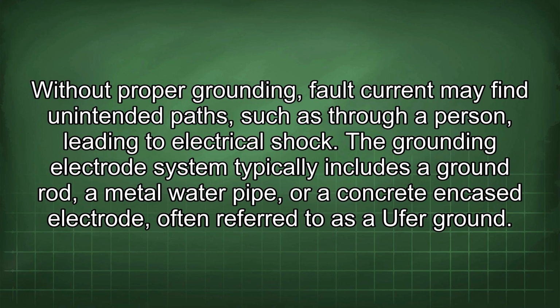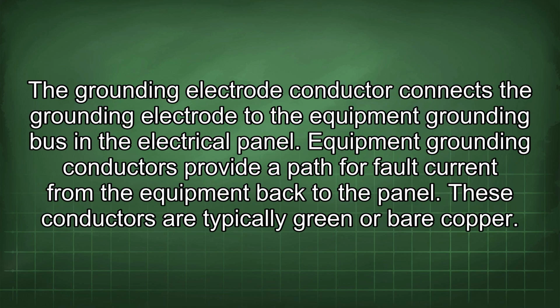The grounding electrode system typically includes a ground rod, a metal water pipe, or a concrete-encased electrode, often referred to as a UFER ground. The grounding electrode conductor connects the grounding electrode to the equipment grounding bus in the electrical panel. Equipment grounding conductors provide a path for fault current from the equipment back to the panel. These conductors are typically green or bare copper.